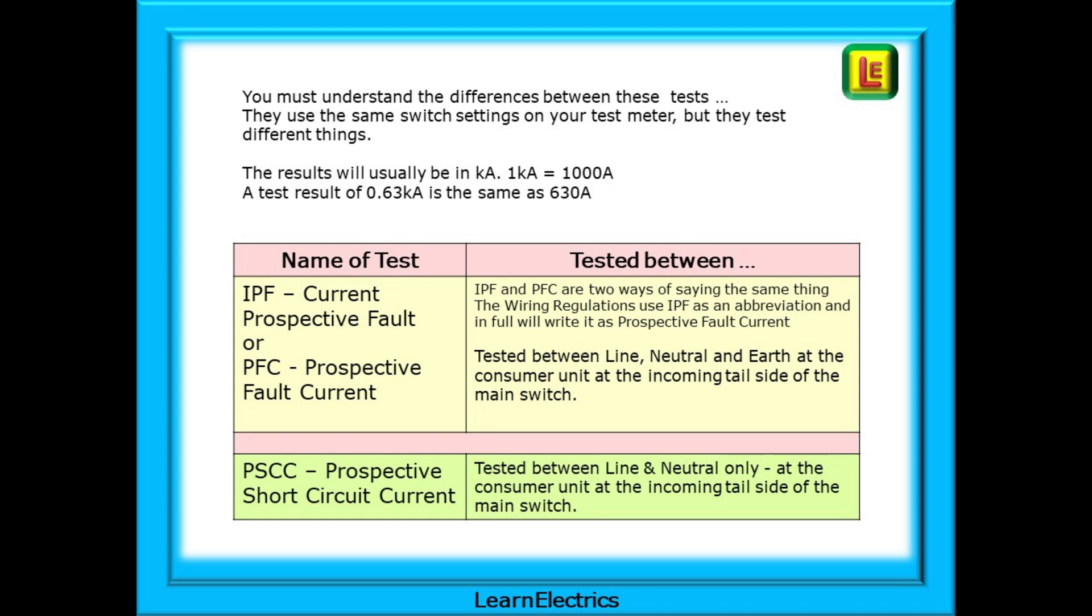IPF and PFC are two ways of saying the same thing. The wiring regulations use IPF as an abbreviation and in full will write it as Prospective Fault Current. It is tested between line, neutral and earth at the consumer unit at the incoming tail side of the main switch. It tells us how much current will flow to earth during a fault.